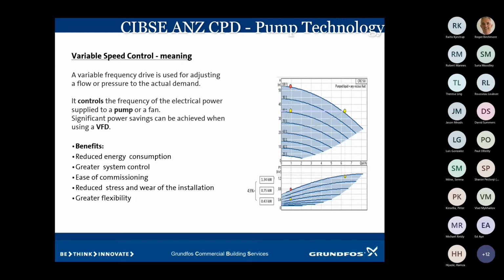If you drop your eye down to the second box below here, you can now see at our peak load where we were doing 6.5 litres a second, we were using about 1.3 kilowatt. If we had a fixed speed pump and we were running up on that high performance curve where the red dot is at the top, we would be drawing about 0.75 kilowatt. But now we're using the VSD and we're following that flat line with the yellow dot. We've dropped our power consumption to 0.43 kilowatt.